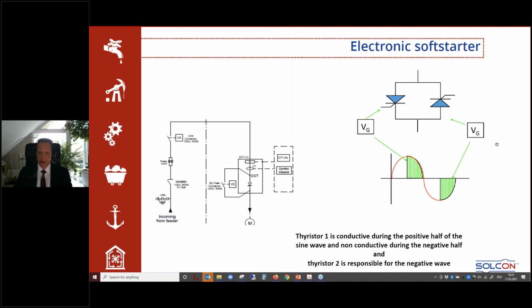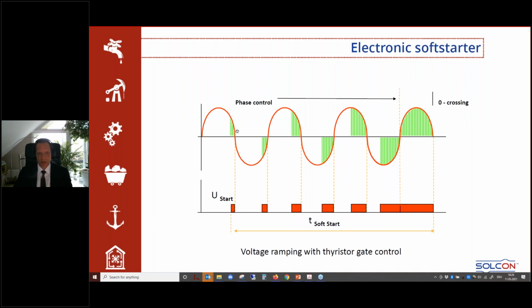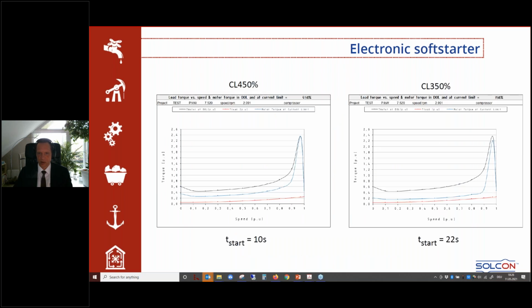The soft starter, the electronics in principle, consists of two anti-parallel thyristors, where this one is responsible for the positive half wave and this for the negative half wave. And the voltage is increased in that way that you are increasing the firing angle of the thyristors. And with this, you have more period of time where the motor sees voltage, which is in principle then gradually increasing the voltage. And when you have the zero crossing, meaning the full half wave, the thyristor is giving the full current and voltage to the motor, which is what we call zero crossing.